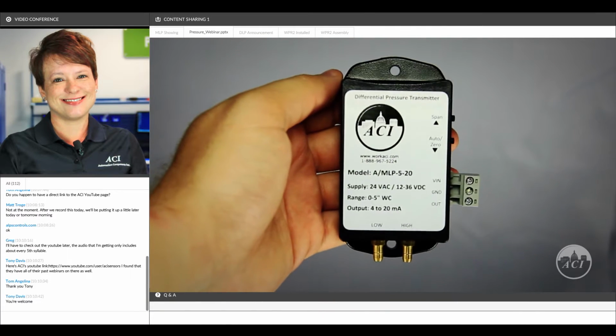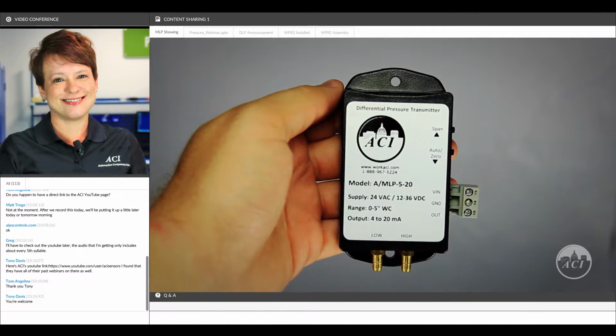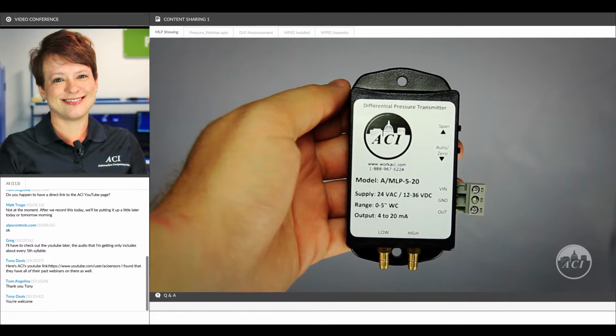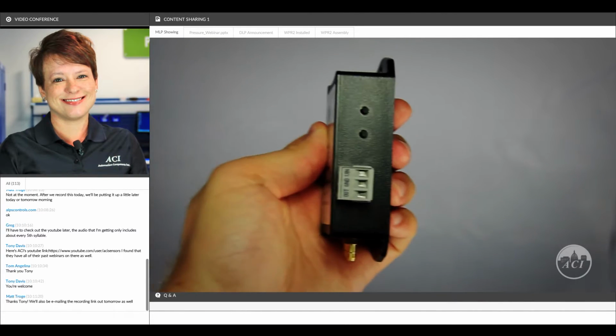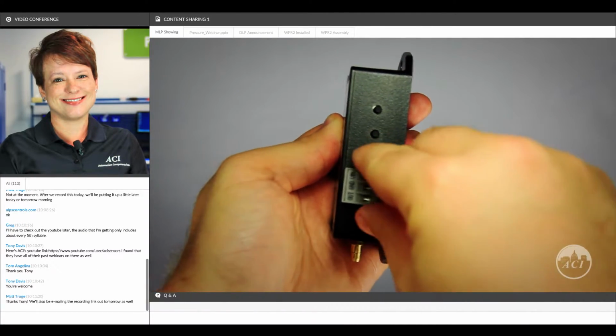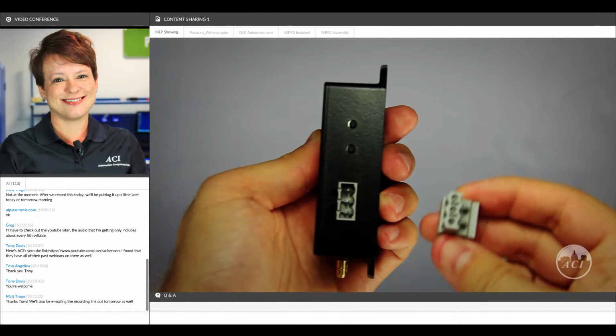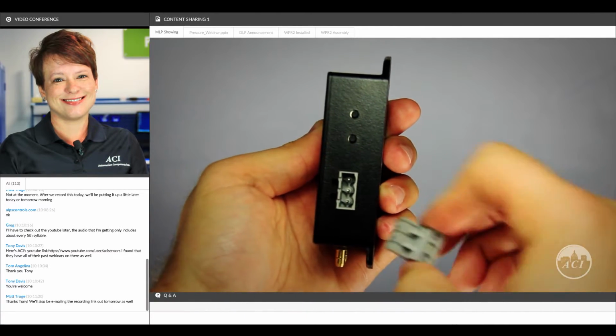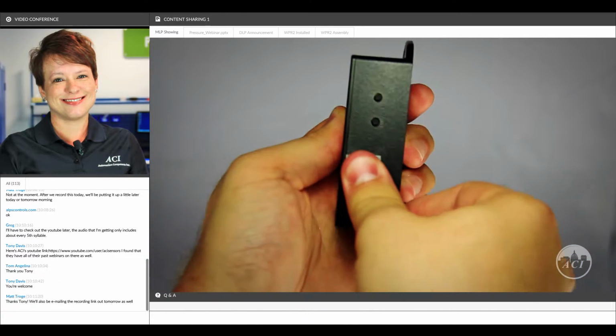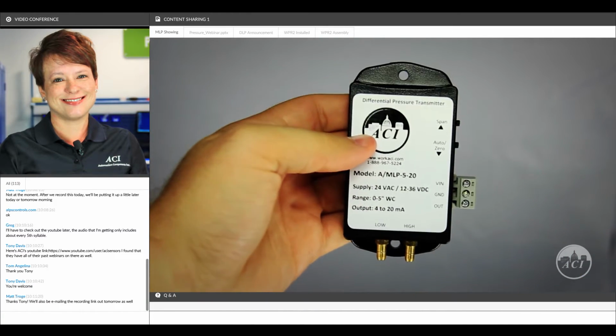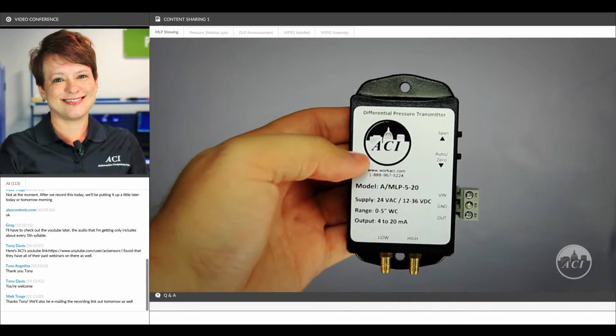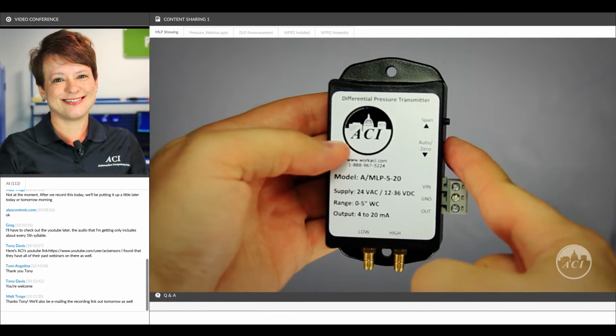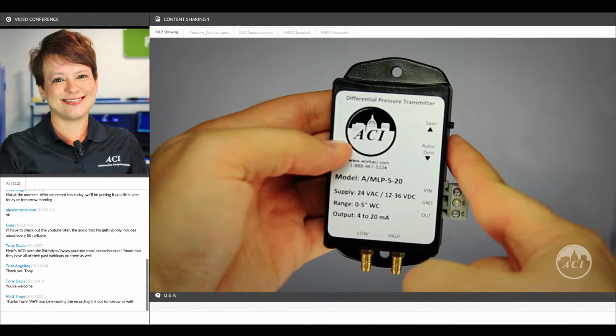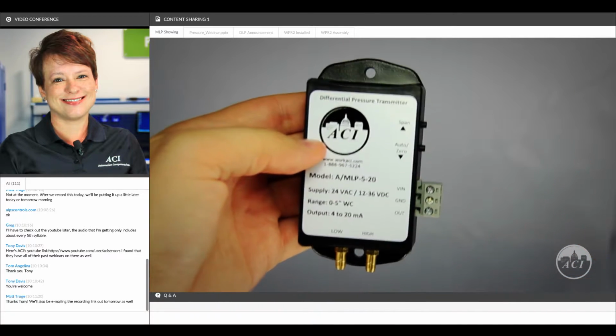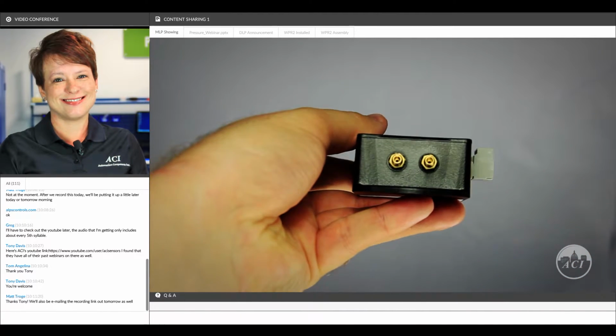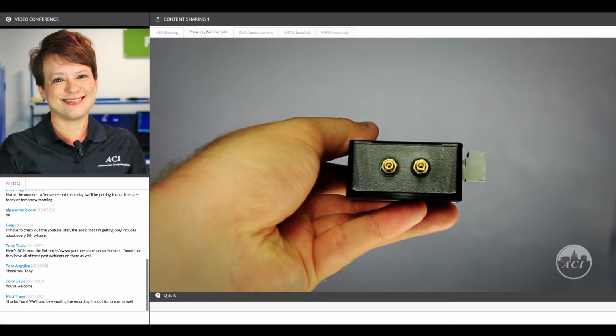So here we have the MLP being held by Matt in our marketing department. You can see that it fits really nicely right on the ends of his fingertips. It does have a pluggable terminal block for your electrical connections, so you can wire it up and then plug it back in, which is very nice if you're in a tight space. It has a push button auto zero feature. Don't let that scare you. You have to hold that button in for a few seconds before it performs the function. And it also has rugged brass ports for your pressure connections.